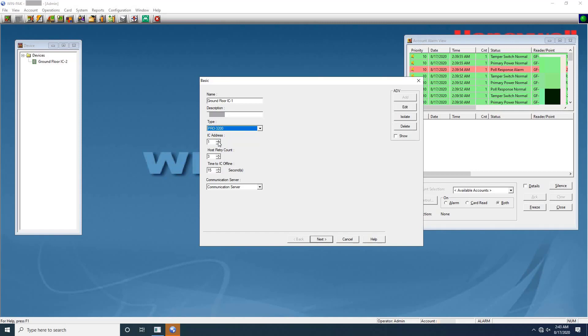In the IC address, enter a unique address of the intelligent controller board. It must be uniquely defined for each panel. Next enter the value for host retry count. The host retry count is the number of times the host computer has to send a command packet to the intelligent controller. Host retry count can be set from 2 to 10, 3 is the default. A range of 2 to 4 is recommended for most applications. Retry counts above 4 would be used in extreme circumstances, such as in a noisy environment. Here I'm not changing the default value.